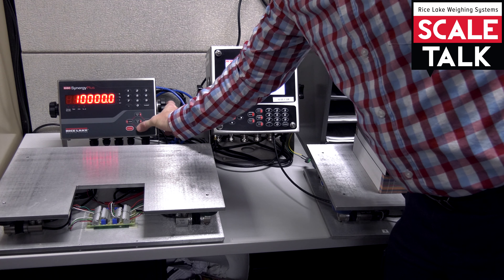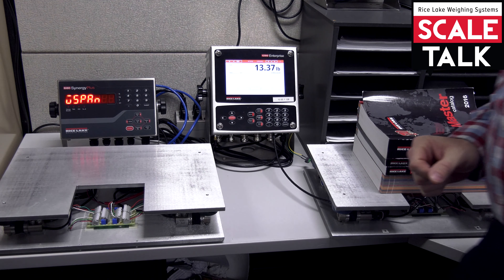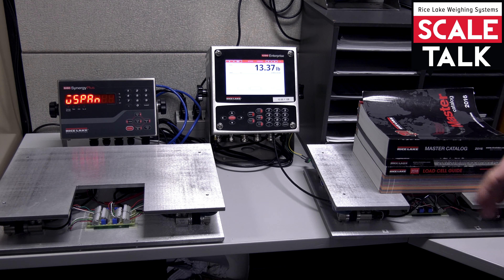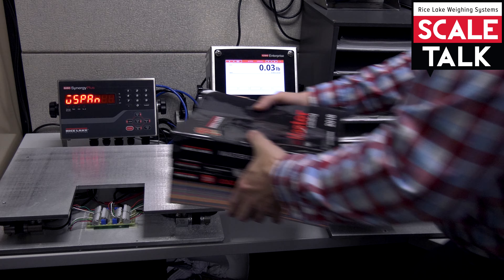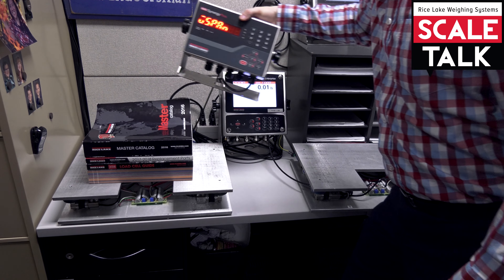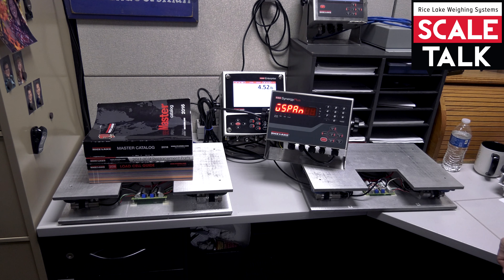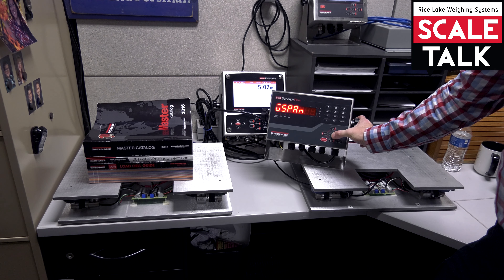We'll go to our WVAL. This is where we're going to plug in our 13.37 that we're seeing on the known good scale. So we'll hit 13.37, then hit tare to accept that value. At this point, we want to make sure we go ahead and put that weight on the scale, so I'm going to move these items and this scale over. Then we'll go ahead and execute our span cal.